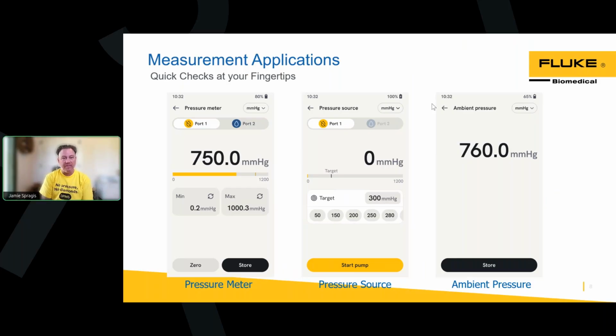The really cool thing about the pressure source is you don't have to reset it if you're taking multiple measurements. So if your pressure measurement has 100, 150, and 200 millimeters of mercury or PSI, whatever that unit is, you can start your pump. When it stabilizes, you can stop it, select another pressure, and then start your pump again, and it'll go up to that pressure, or it'll deflate to that pressure. So you don't have to start and stop.